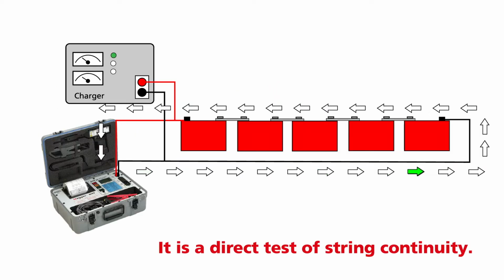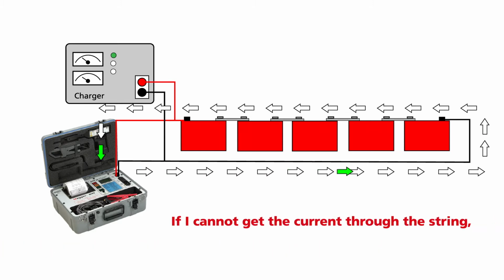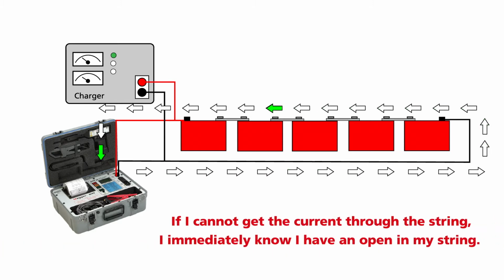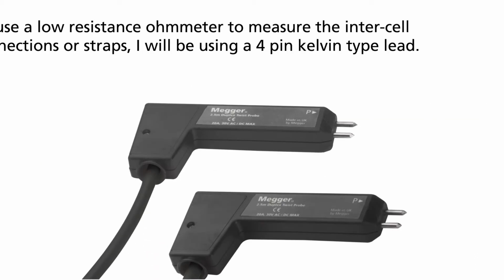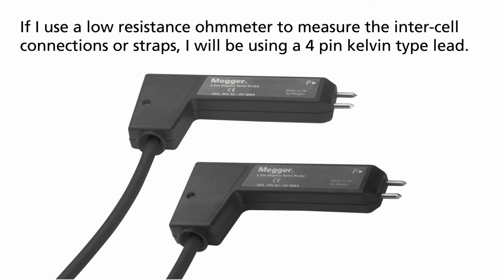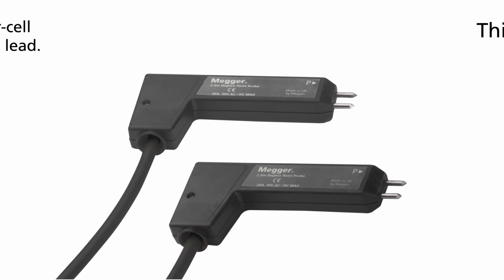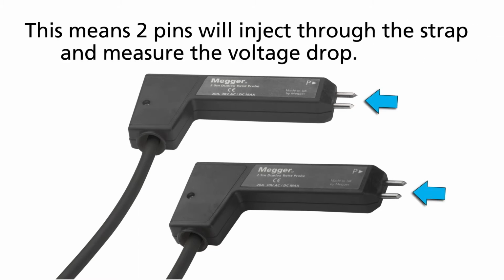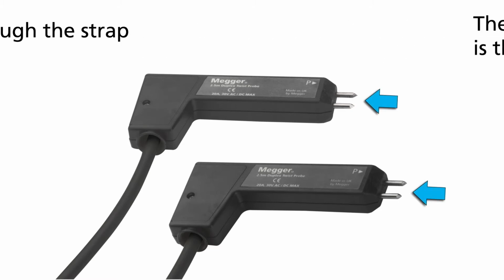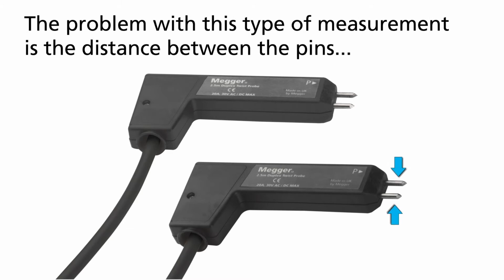There are several advantages to injecting current through the entire string. It is a direct test of string continuity. If I cannot get current through the string, I immediately know I have an open in my string. If I use a low resistance ohm meter to measure the intercell connections or straps, I'll be using a 4-pin Kelvin type lead. This means 2 pins will inject current through the strap and 2 pins will measure the voltage drop.